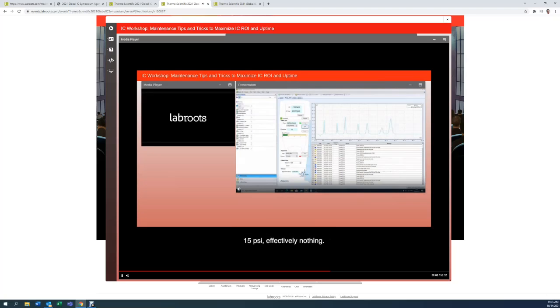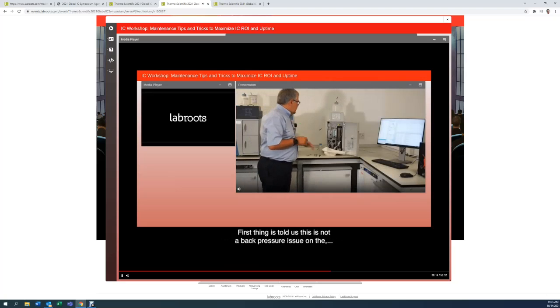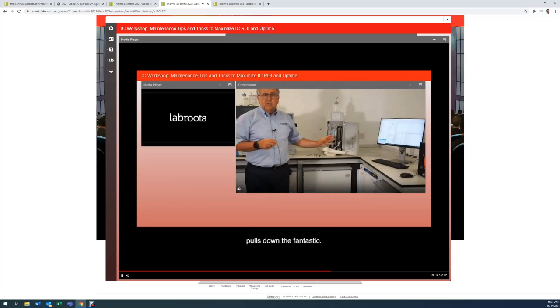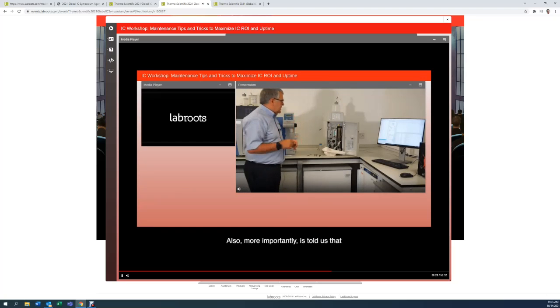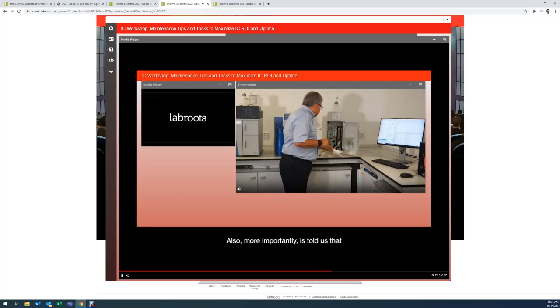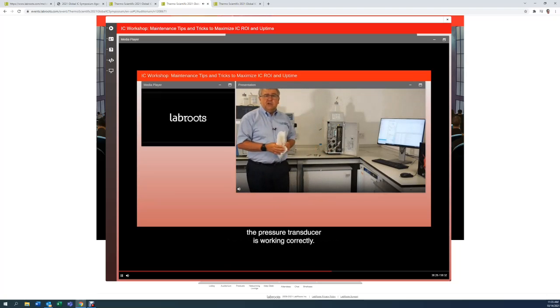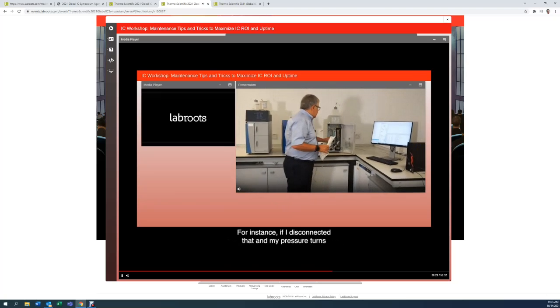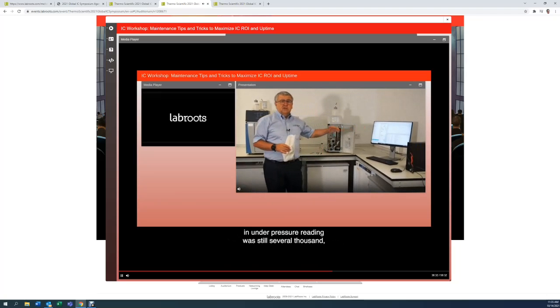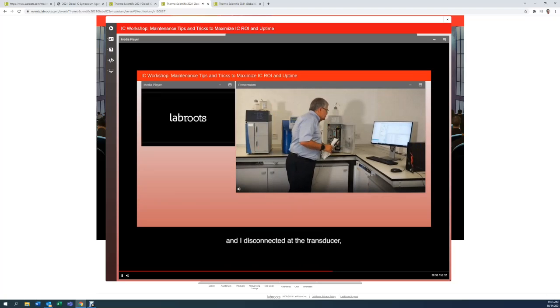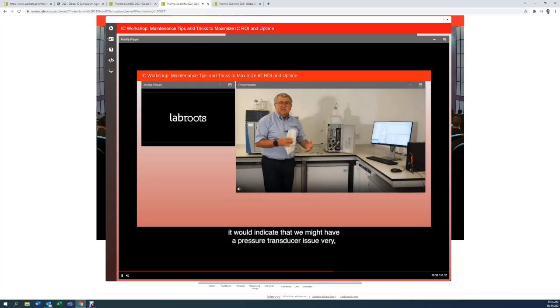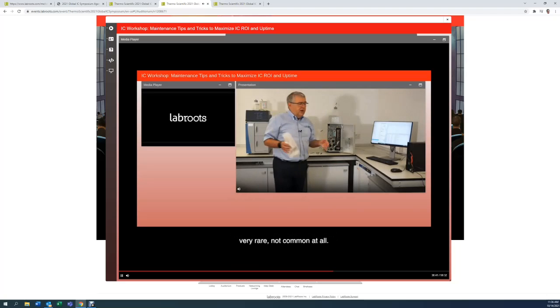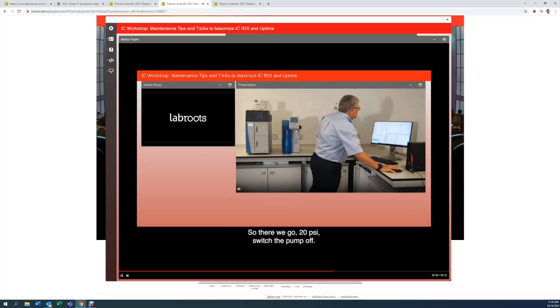15 psi. Effectively nothing. Now that's told us two things. First thing it's told us is there's not a back pressure issue on the pulse dampener. Fantastic. Also, more importantly, it's told us that the pressure transducer is working correctly. For instance, if I'd disconnected that and the pressure reading was still several thousand, and I disconnected at the transducer, it would indicate that we might have a pressure transducer issue. Very, very rare, not common at all, but again, something that we could look at. So there we go, 20 psi, switch the pump off.